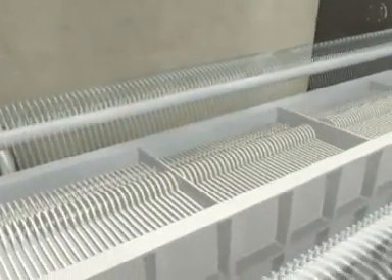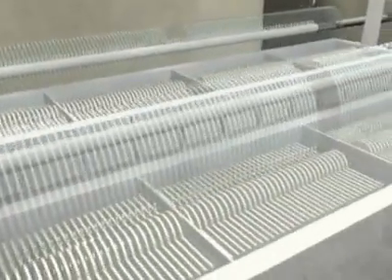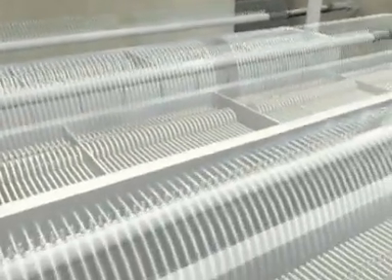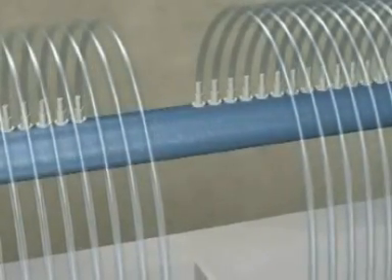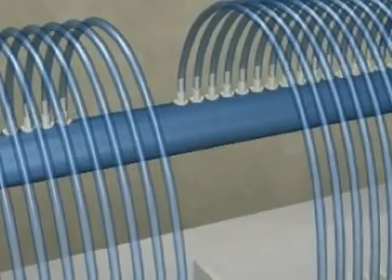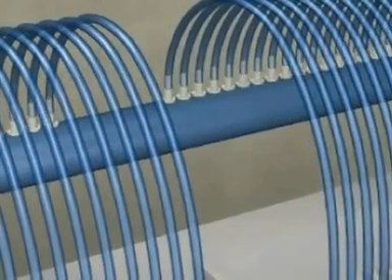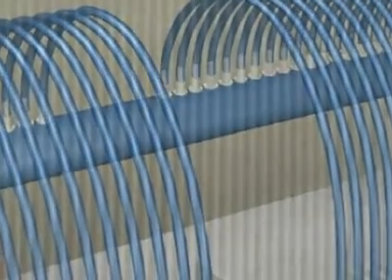The number of membrane units sited in the membrane bioreactor does not alter the required head, thus enabling the process to be scaled up without any significant issues. Cleaning of the membranes is undertaken using a dilute sodium hypochlorite solution, which is introduced into the membrane as a simple backwash. Under normal operation, this cleaning need only take place twice a year.